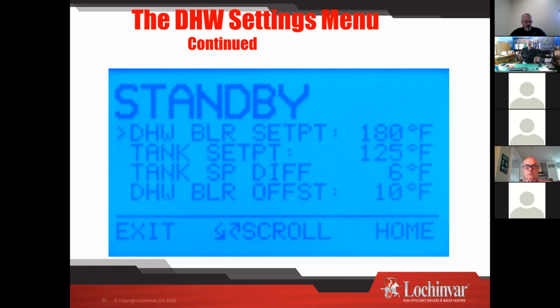Tank set point differential, that is, so 125 degree tank set point, a 6-degree differential. That means at 119 degrees in the tank, the boiler is going to kick on to put that water out, or turn the boiler on. Where would I adjust that differently? The question really becomes, where's the sensor in your tank? If my tank sensor is higher, my differential is probably a little tighter because I want it to come on sooner because I've already burned through the bottom of my tank. For Lochinvar, our tank sensors happen to sit pretty low in there, so we can run a little wider. In fact, you'll find most of the time when our tank sensor sees that colder water, we hit that differential. If you were sensing the top of the tank, it is still probably above the tank set point temperature because we have such a broad range. So just look at wherever your sensor is within the tank.